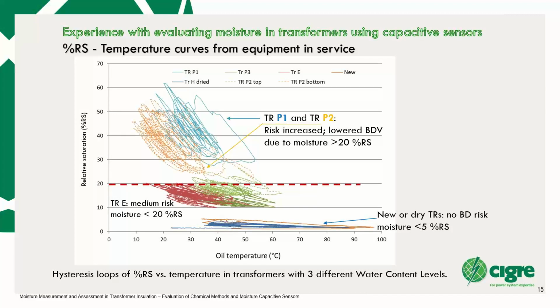On this graph, we have three major cases. The first case are the transformers just at the bottom, which are very dry. In this case, we have moisture which is much below the 20% as absolute value of relative saturation. And then the second thing we see here are very, very narrow hysteresis curves. The second case, these are transformers which are in service, which are safe, but which have, because of their long operation, some moisture. There are two transformers just below this red curve of 20%. There again, both of them are in absolute values below 20%, and they again have hysteresis curves which are not broader than 15% relative saturation.